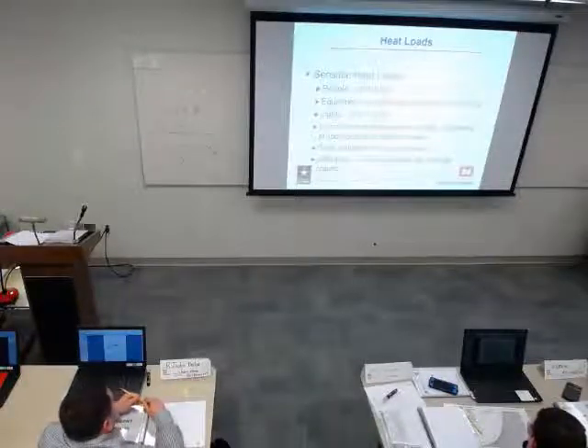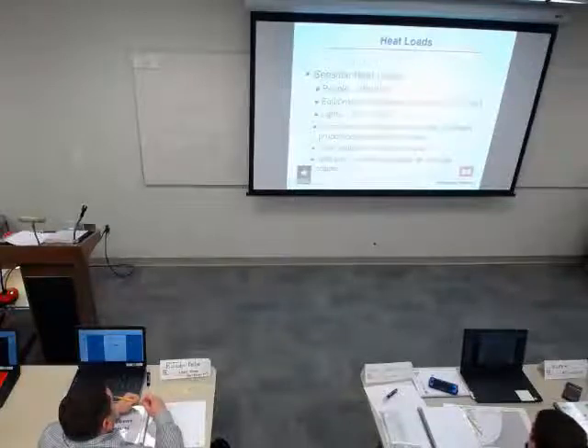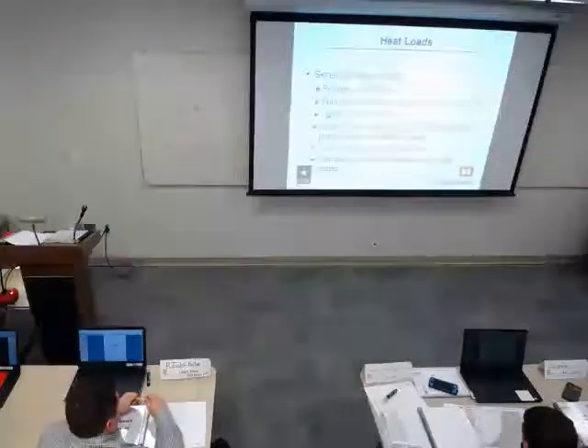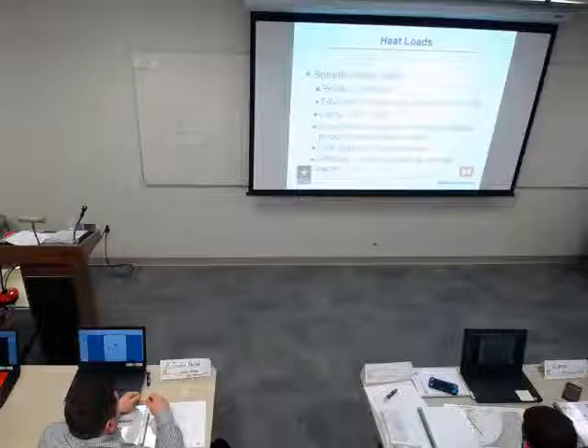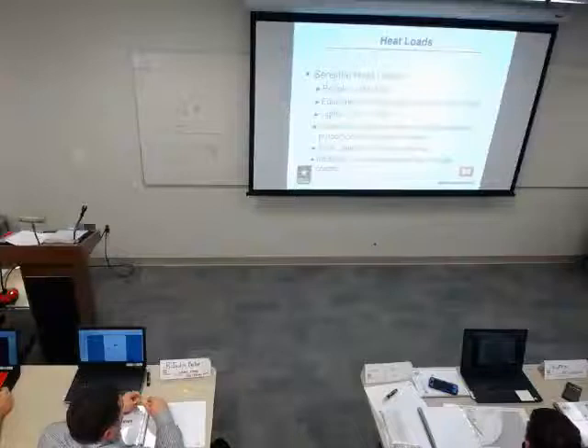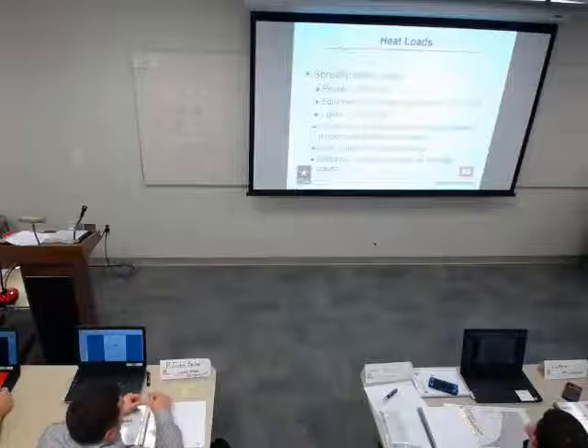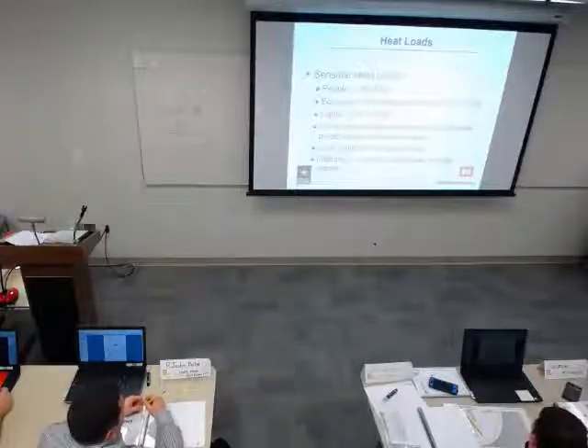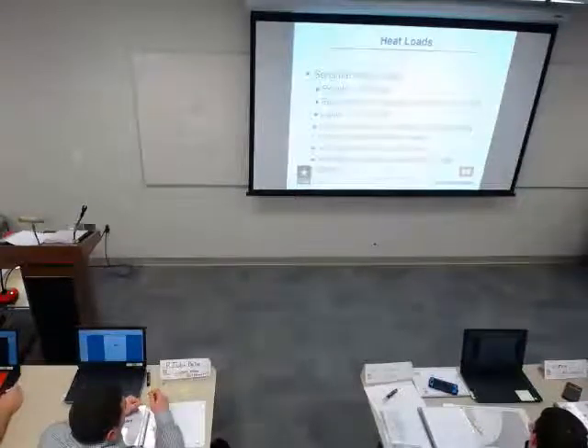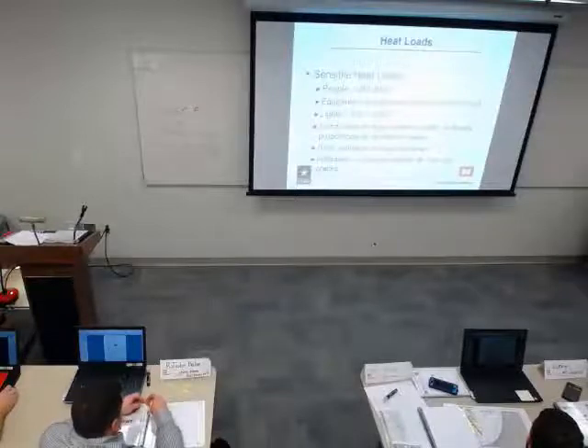So let's first of all look at sensible. We've got people. A typical person gives off in an office environment about 250 BTUs per hour. Equipment, from computers, printers, and all the other stuff you have in the office, we've got between a half and 1 watt per square foot. Lights, 0.5 to 1 watt per square foot. That number is coming down. Come to our design class, we'll tell you how that impacts life. Conduction through exterior walls. We know the more insulation you have, the less heat gets conducted through the walls. And then we have the solar radiation to the windows, and then infiltration.